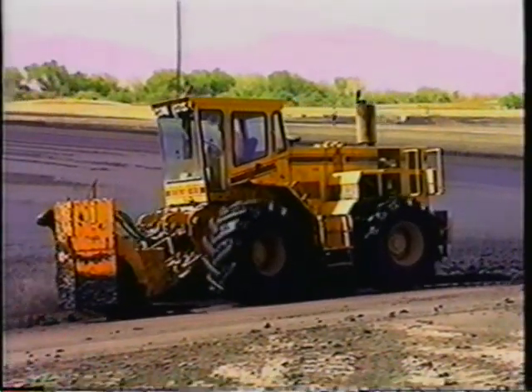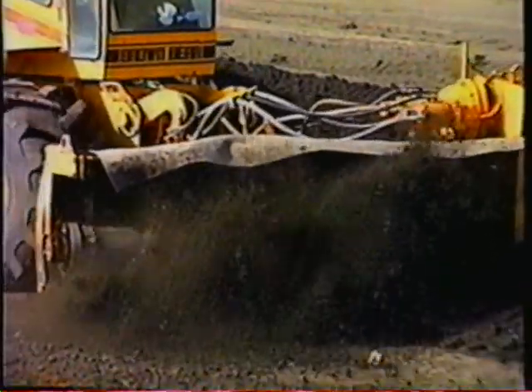My name is Keith Greenberg. I'm the Assistant Wastewater Superintendent for the City of Phoenix, Multi-Cities 91st Avenue Wastewater Treatment Plant, located in Phoenix, Arizona. The process we use is a combination of mechanical and solar drying. The very hot temperatures allow us the great ability to do solar drying, and then we use a farm tractor to help turn the sludge and get it a little bit drier, and then the Brown Bear picks it up at about 15 to 18% dry and dries it up to 40%.